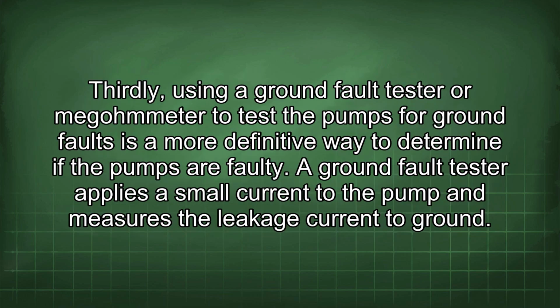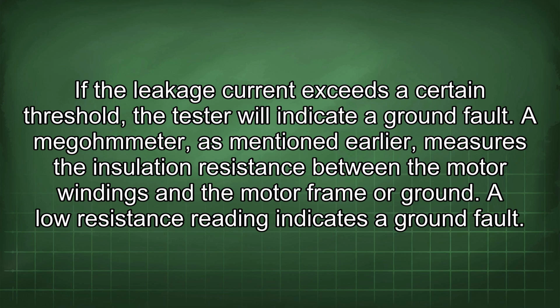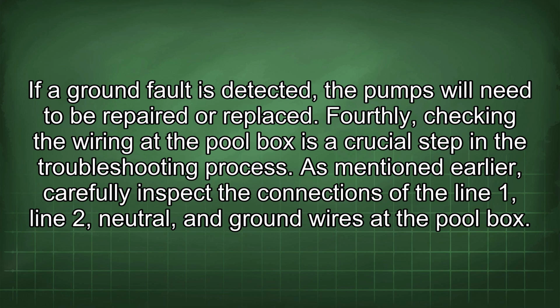Thirdly, using a ground fault tester or megohmmeter to test the pumps for ground faults is a more definitive way to determine if the pumps are faulty. A ground fault tester applies a small current to the pump and measures the leakage current to ground. If the leakage current exceeds a certain threshold, the tester will indicate a ground fault. A megohmmeter, as mentioned earlier, measures the insulation resistance between the motor windings and the motor frame or ground. A lower resistance reading indicates a ground fault. If a ground fault is detected, the pumps will need to be repaired or replaced.